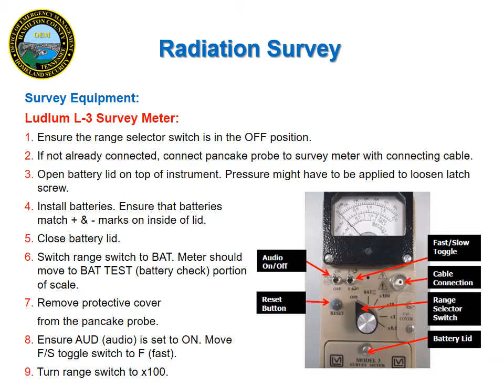When connecting the cable, make sure the cable is locked in place before you use it. You can check this by pulling on the cable to ensure that it does not come loose. If the cable is loose, twist the cable connections to lock them in place. Next, open the battery lid. Again, this is located underneath the handle. Do not open the latches on the ends of the monitors. The battery slot is always going to be located under the handle and will have a silver twist knob.